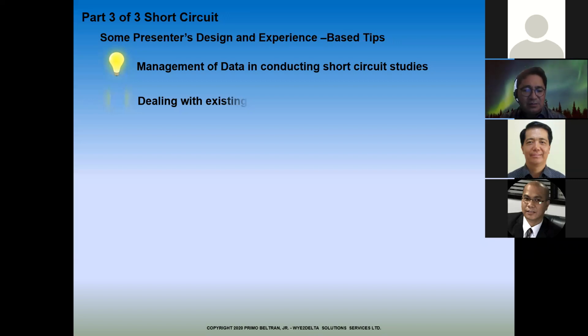I was under the impression that when you activate the IS limiter, aside from opening the fuse, there will be a reactor that will replace it, so that it may operate fast enough that when the fuse opens, there will be no tripping, but the fault current will be limited. The buses will be divided, instead of being one bus.